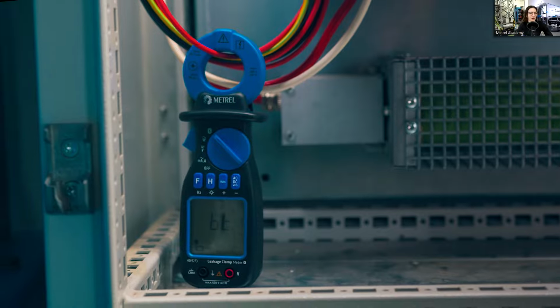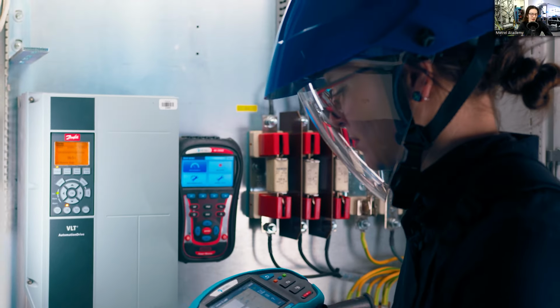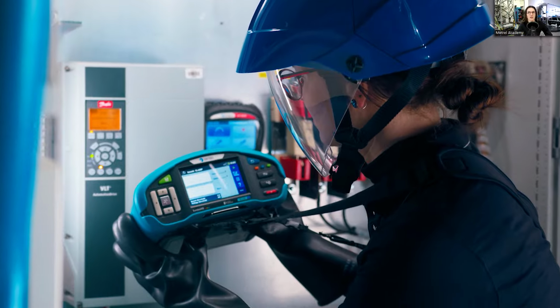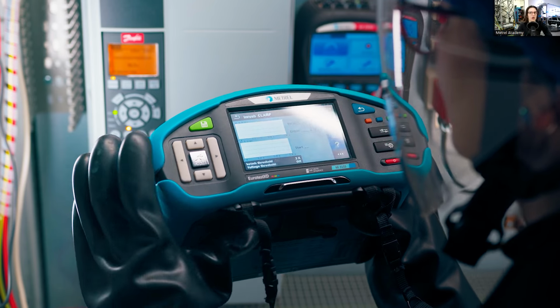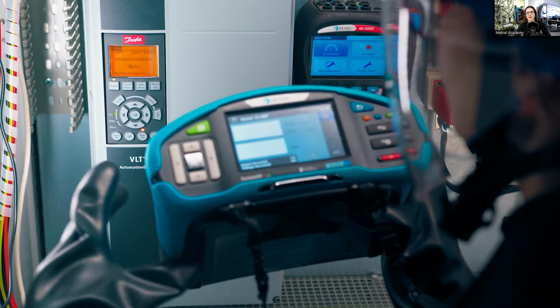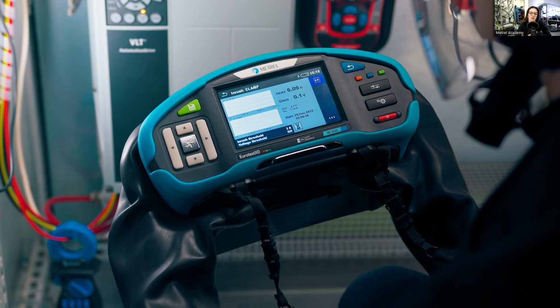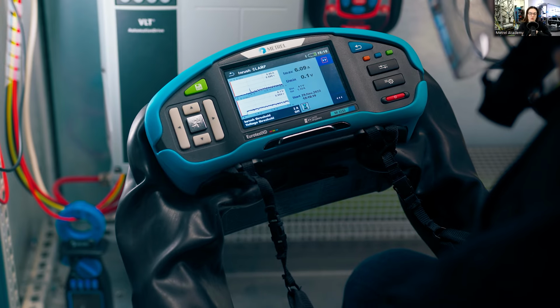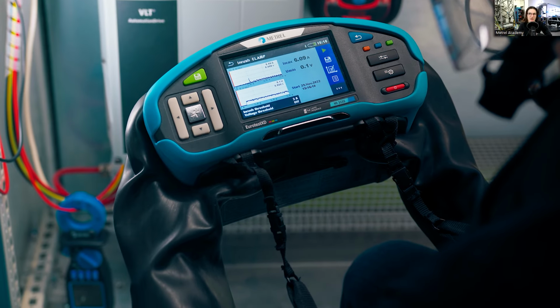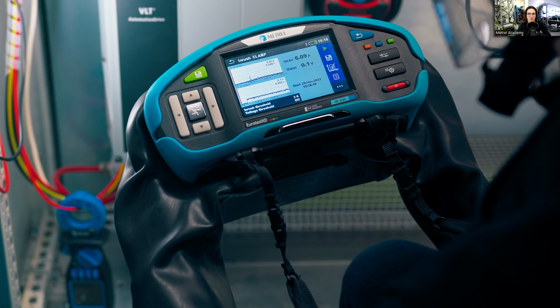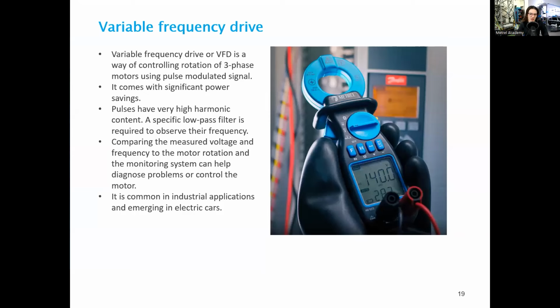So let's look at the video of how to measure the inrush current. We have a motor here and easily accessible supply wires. So we set up our clamp to measure the current. We set up the instrument again with the trigger so that it waits for the trigger value. And here we can see how the graph is shown. Now, the graph is going to show us the recording about 1 second before the threshold was passed, while the length of the graph, so how long after the threshold is measured, can be set up.